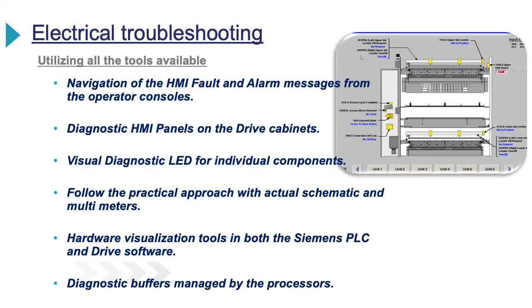During the training, we will start with the hands-on practical approach of troubleshooting with schematics and multimeters. We will utilize tools available from the operator screens as faults and alarms are displayed for both the operators and the technicians. The PLC module that generated the fault along with the actual tag will help the tech narrow down the problem along with the fault history library displaying details and the time of the error.